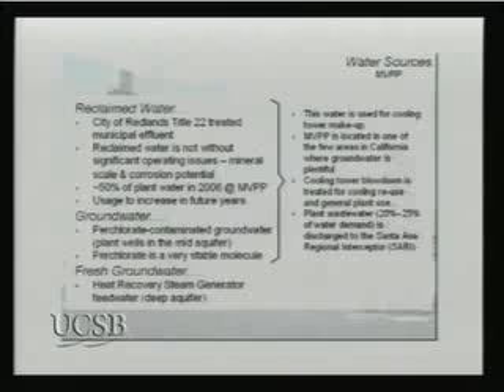The one thing about reclaimed water is it's way saltier, it's got stuff in it, it's got organic matter in it, and it creates problems with scale and corrosion, which is a big deal in a power plant. The thing underneath the steam turbine that condenses the steam - corrosion's bad there. Scaling is bad because it makes those tubes less efficient; they get plugged and fouled. The plant becomes less efficient and uses more energy to make the same number of megawatts.